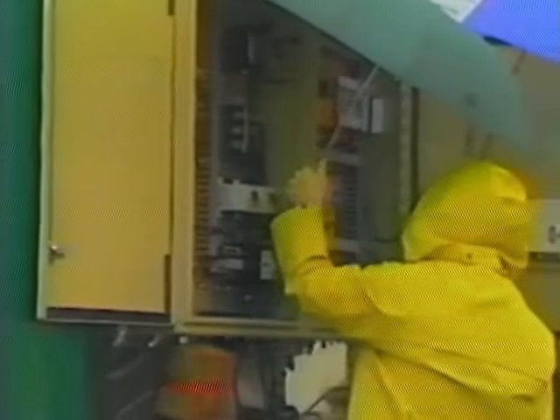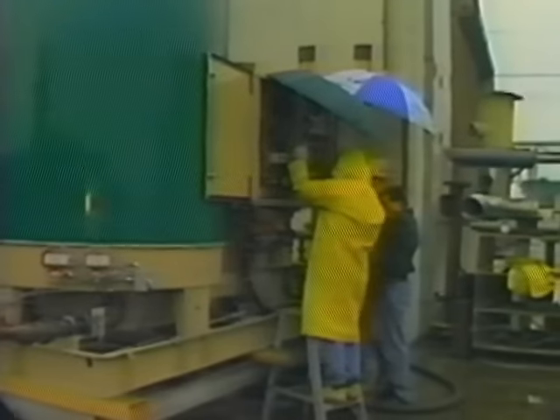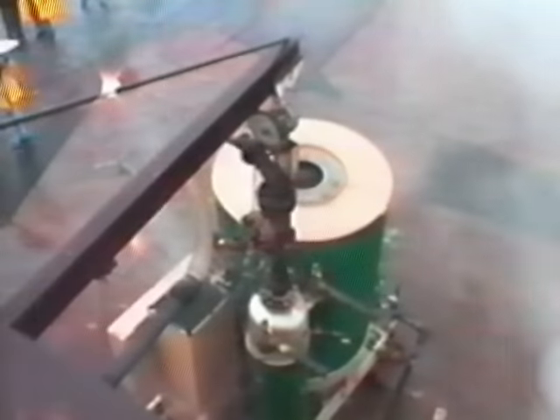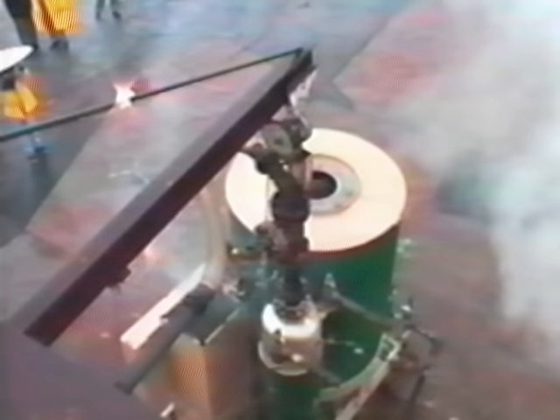In this case, these devices were removed from the unit and thus allowed the burner to continue to fire uninterrupted. What you will see in the next few minutes is the full destruction of the steam generator pressure vessel without any danger from a steam explosion.